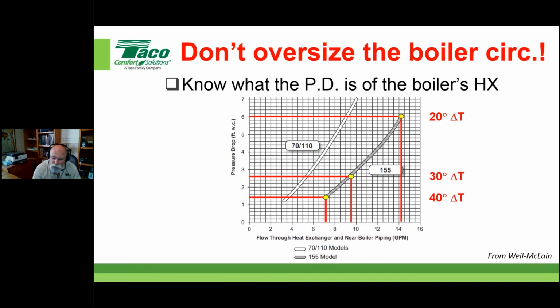Here's one thing I do want to point out. Some boiler manufacturers, including this one, will actually throw a little fudge factor in there. It's not really a fudge factor. They're actually anticipating a certain amount of piping, valves, fittings, apparatus, incidentals on that piping, that gives you a total pressure drop through the heat exchanger. Now, don't put the belt and suspenders on here, right? If you know they make this note here and they're mentioning near boiler piping, then don't add additional pressure drop for that. It leads to circulator oversizing, just like we always talked about.